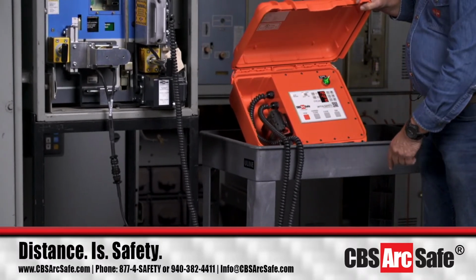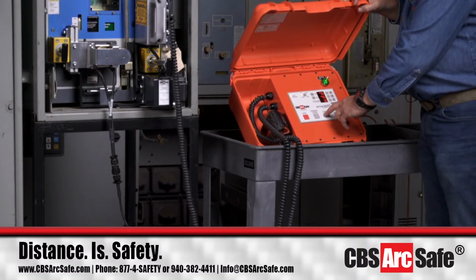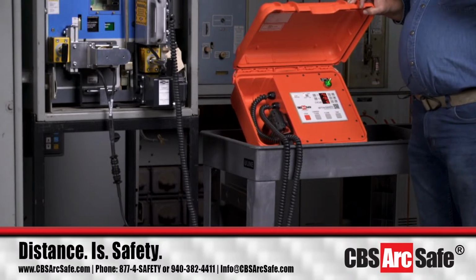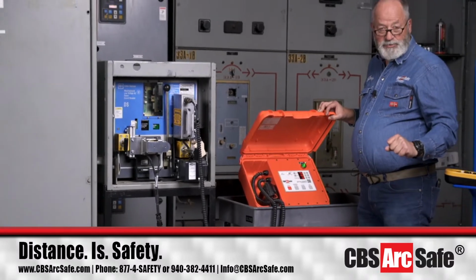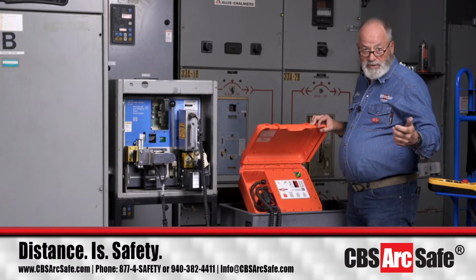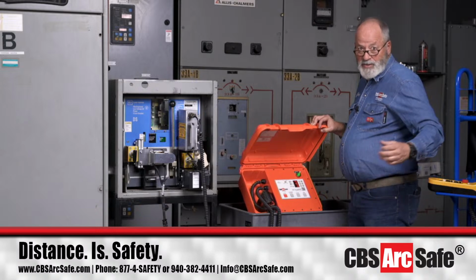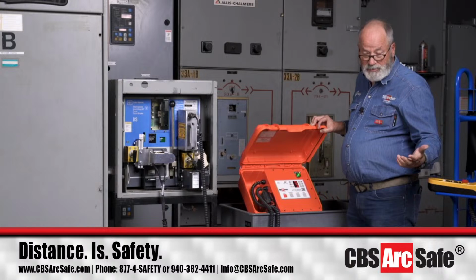Okay. Now, if you haven't seen this before, this is labeled charge close, close, and trip. And if you ask why it's charge close, old ITE K-line breakers, you pull that handle down at the bottom of the stroke, the breaker closes. Okay. An old GE AK1, AK2, AK2A, AK5, you move that handle up, it comes back down, it closes right at the bottom of the stroke.